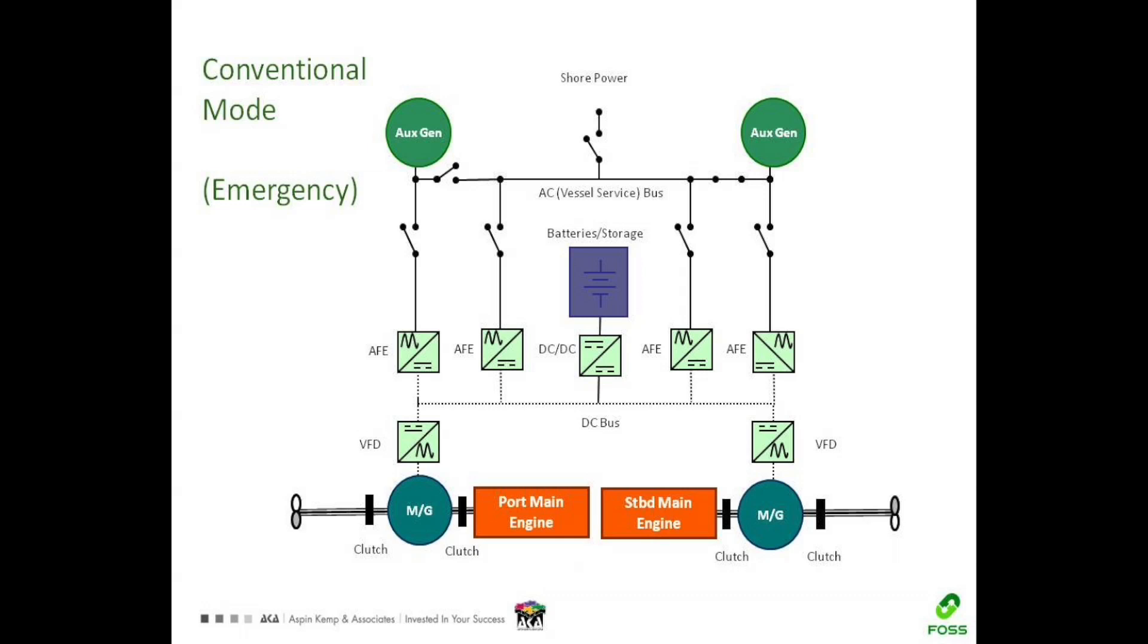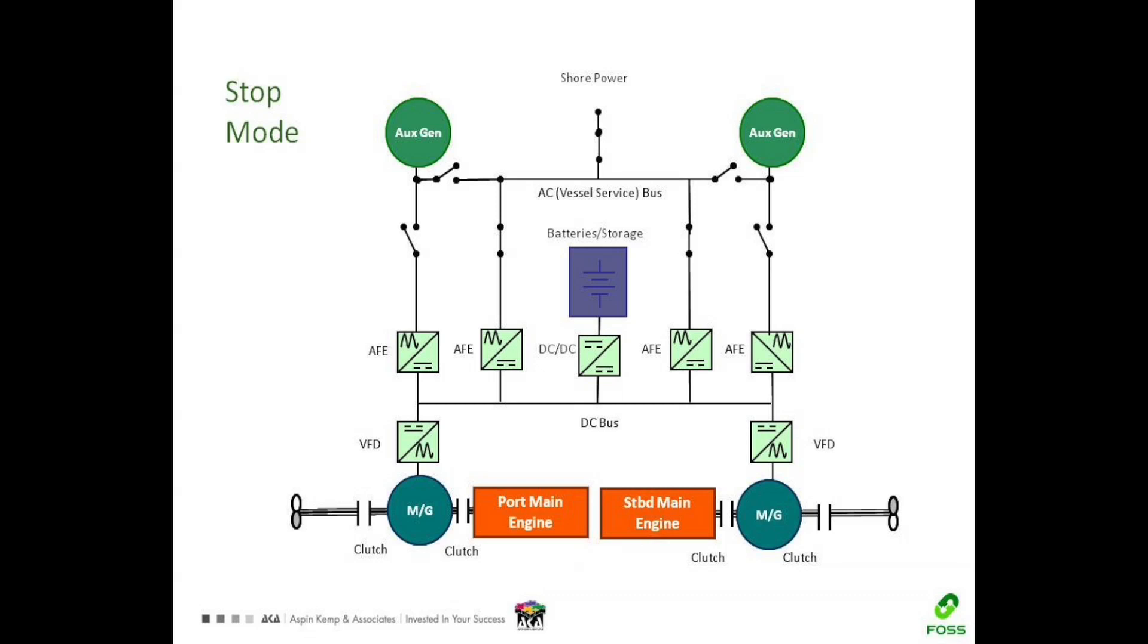So in that mode, the propellers get power directly from the main diesel, and one of the auxiliary generators will be providing power to the AC bus as it would on a conventional vessel. Stop mode, that's when the vessel might be at dock tied up at its normal berth or at another dock in the harbor. In that mode, if it's at its own dock, then it might be on shore power. In this mode, the main difference of operation is that the propulsion units are disabled. So you get power from shore power, come through and supply the AC bus, through one of the AFEs to the DC bus, and then you can charge batteries.